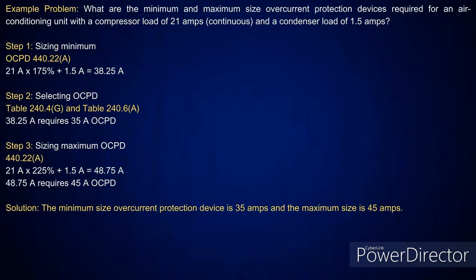The same thing applies here when I'm doing the overcurrent device. You take the largest at 175% for this case for the AC unit, and then you add the condenser on at 1.5 amps. Okay, so I take 21 amps at 175% and add that 1.5 onto it. That gives me 38.25 amps. Now I just read to you, it says it can't exceed the calculated value. So I look at Table 240.6(A), the next size below that is a 35 amp.